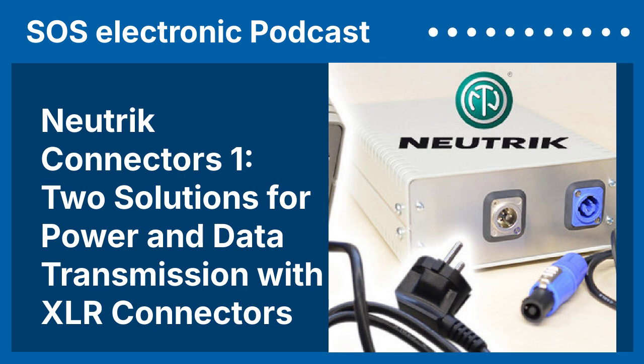Selection of a suitable connecting cable. Another important part of any solution is to find a suitable connection cable, which can be even more difficult than finding a suitable connector. For my application, I need a combined cable made of a twisted pair cable with a small cross-section with a characteristic impedance of 120 ohm for data transmission. For energy transmission, I need a twisted pair cable with a larger copper cross-section. It is advantageous if the entire cable is shielded.